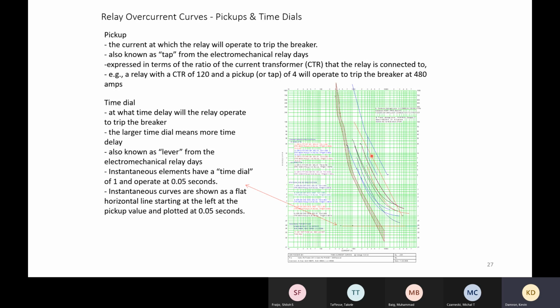This diagonal line here is the conductor damage curve. So we're making sure that we're protecting the conductor that's out there. And this, again, I think came up in some discussion. A lot of utilities practice that the protection is there for faults. We're there to protect this conductor from a fault. We're not there to keep you from overloading the conductor and burning it down.